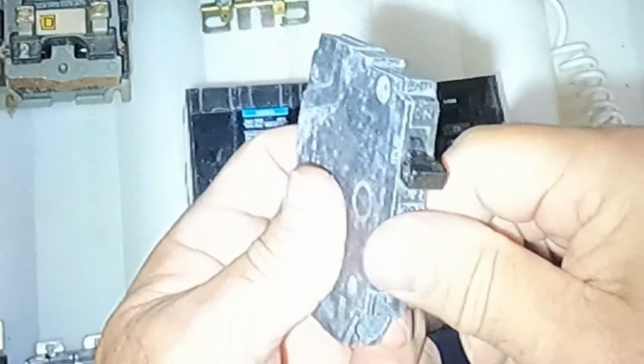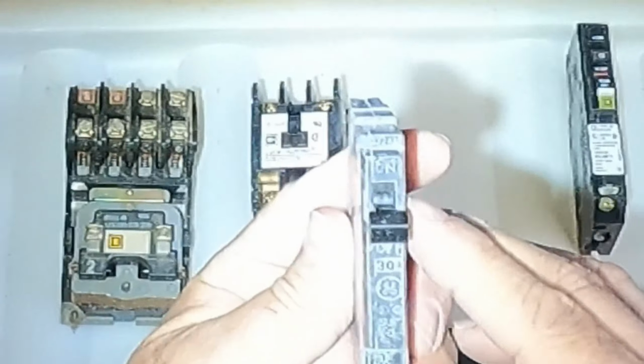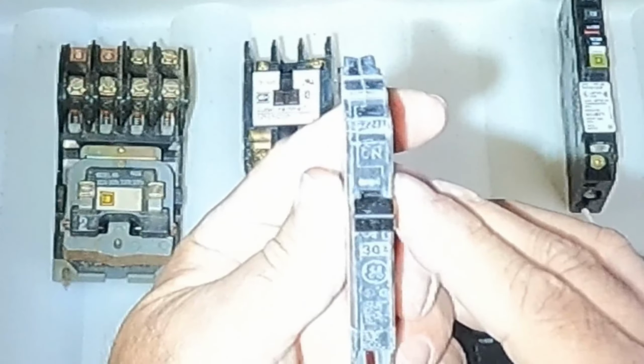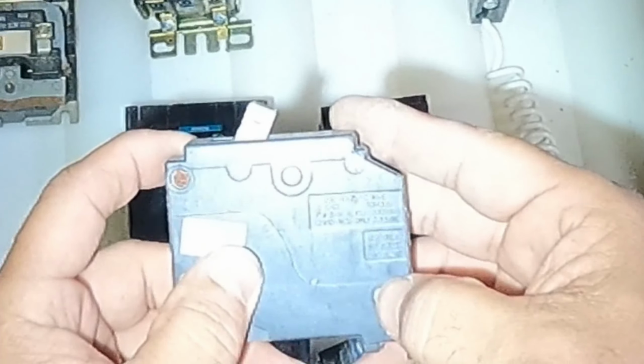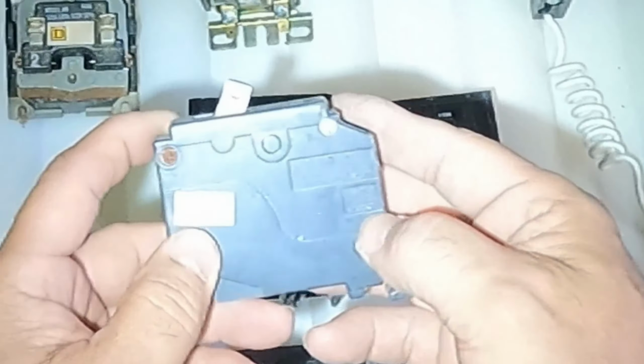Here's a slimline breaker you guys might have. I see some lettering here. Again, as long as it's rated and it's listed for its use, you could use it. No, this is not rated, obviously. Look how small that is. But that's a 30 amp rated thin breaker. Cutler Hammer. Cutler Hammer clearly says use only in listed enclosure. That means you can't use this on its own. You can't fabricate your own type of enclosure anyway. And it says here, max RMS 10,000 amps, 10 KAIC, 120/240 volts. So no, you can't use this.